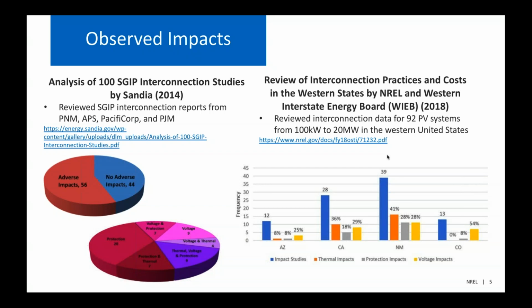One of these was a report on SGIP interconnection studies. They looked at 100 different studies, and this was performed by Sandia and included a review of interconnection reports from PNM, APS, PacifiCorp, and PJM. Out of all the reports that they reviewed, they saw that 56 had adverse impacts from the interconnection of these larger PV systems, and 44 had no adverse impacts. And you can see in the pie chart below the distribution of different impacts that were observed. There's a split between voltage, protection, and thermal impacts, and in some cases multiple impacts were observed.